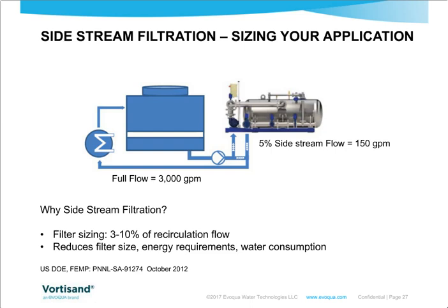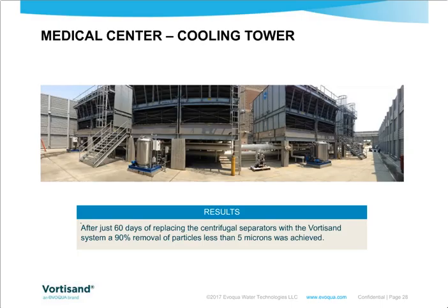So by installing a side stream filtration in this medical center's cooling tower, they were able to achieve drastic reductions in particle counts. After just 60 days of running the Vortisand filter, they achieved 90% removal of particles less than 5 microns. And you can see here the image of the four cooling towers, a panoramic view of each cooling tower having its own 150 GPM side stream filtration.